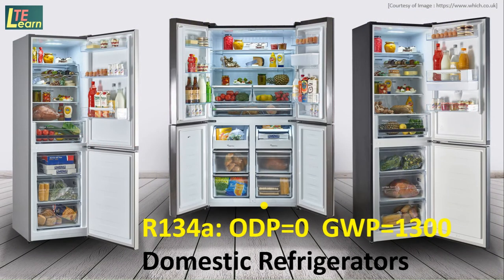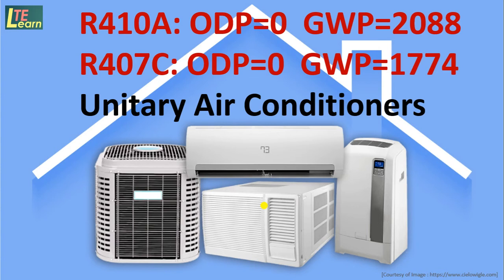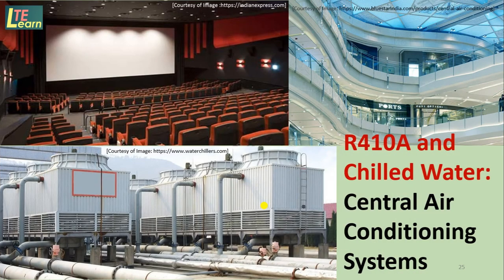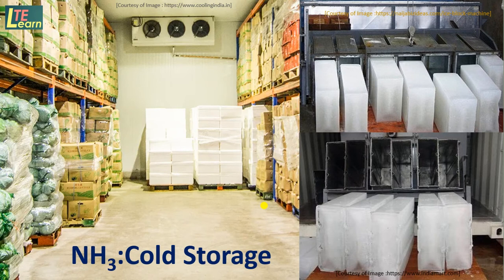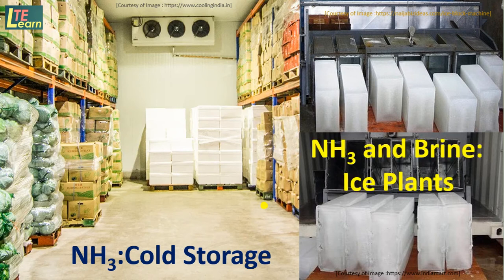Refrigerant R134a, also called tetrafluoroethane, has an ODP of zero and is used in domestic refrigerators. Unitary air conditioners use refrigerants R410A and R407C. Refrigerant R410A is used as a primary refrigerant in central air conditioning systems, while chilled water is used as a secondary refrigerant. Ammonia is used in cold storage, and ice plants use ammonia as a primary refrigerant and brine as a secondary refrigerant.